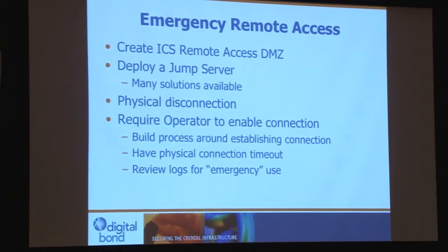And then also this emergency remote access should be logged, and you should have a process for reviewing that log. So if the operators are turning this emergency remote access on 3 times a week, you don't really have emergencies. You have a fragile system. You have a system problem that you need to diagnose and fix.